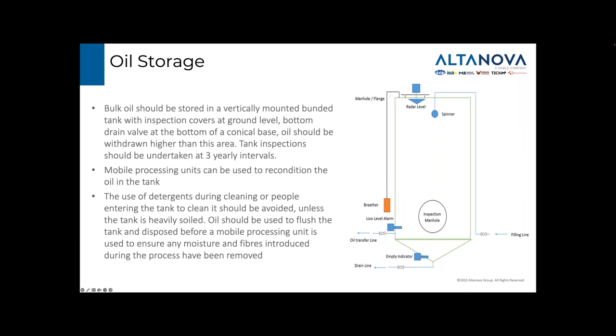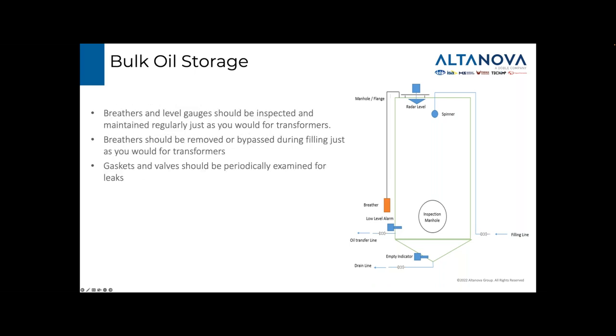However, cleaning with detergents or having people inside the vessel should be avoided, unless the tank is so soiled that the oil processing alone would not be sufficient to clean the tank. Maintaining the bulk storage should be dealt with in the same way as a transformer, with visual inspections of the tank and bund integrity, paintwork, gaskets, valves, gauges, and breathers. Remember to temporarily remove or bypass breathers during filling or rapid draining to prevent damage to these components.